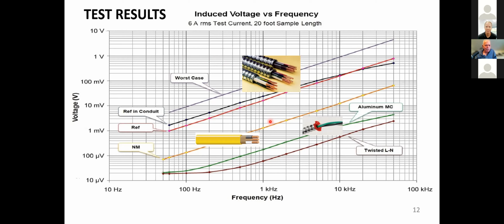It turns out the magic bullet here: ROMEX gets better, and type MC, this aluminum-clad pre-twisted stuff, but it unfortunately includes the ground wire in the twist. It's better to let the ground wire run its own course and not twist it. But when you twist the two current-carrying conductors, you put them as close together as possible, which tends to cancel.